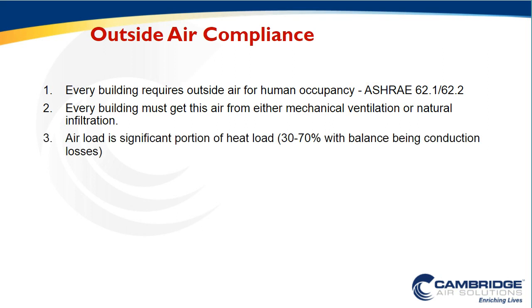And now from an energy efficiency perspective, if we look at these large warehouses and high bay spaces, the heating requirement to heat the air from outside conditions to space conditions is what we call the air load. And in these large buildings, this air load can be a massive percentage of the overall heat load in a large warehouse or fulfillment center. So let's talk about what is the most energy efficient way to heat the air load in these spaces. Well, let's take an example.